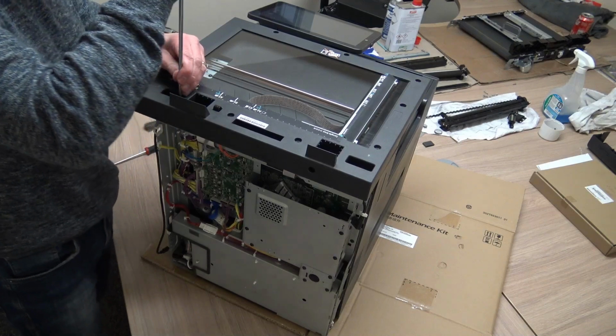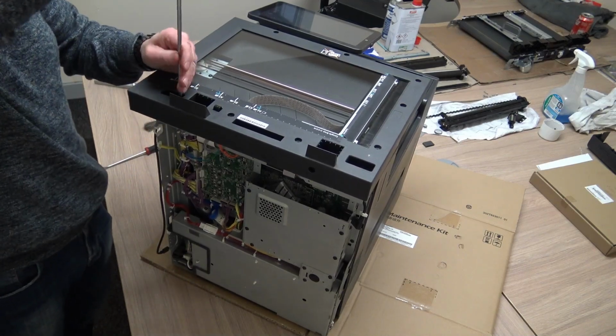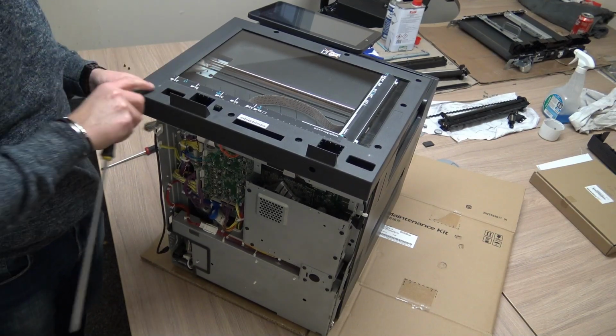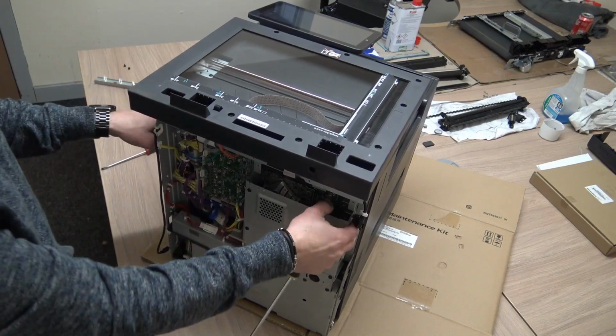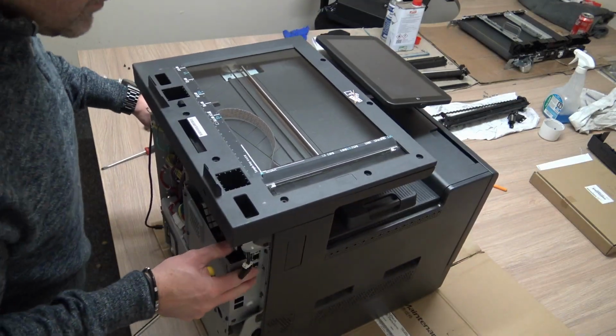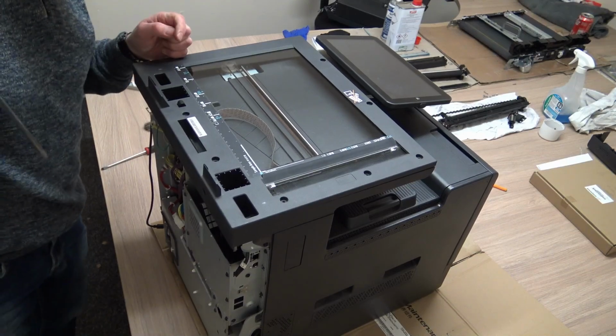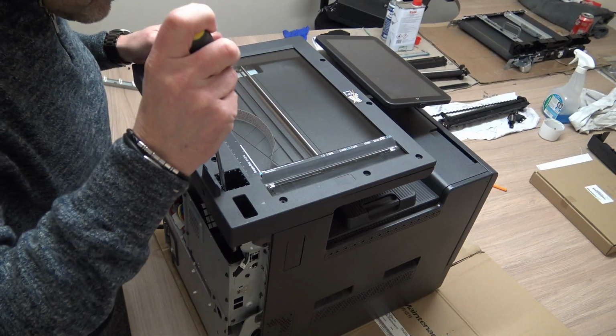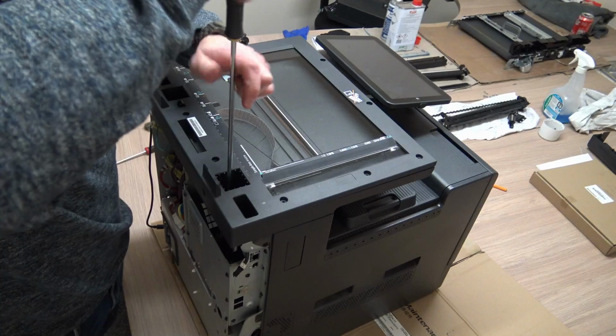Now we're going to take the top of the scanner unit off. Basically it houses the platen, which is that big piece of glass in there. So some of the screws have already been taken out before I touch the machine. There's the 3 at the front at the top, and then the 2 at the sides and the 2 at the back on the top.